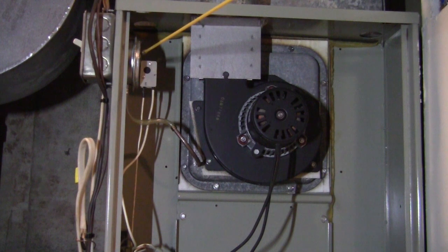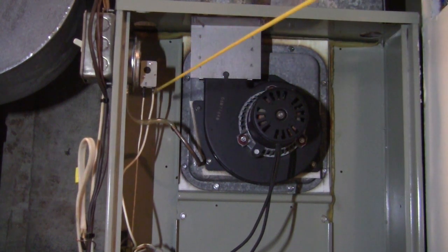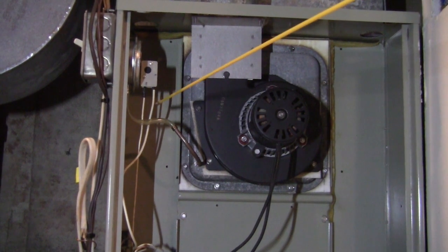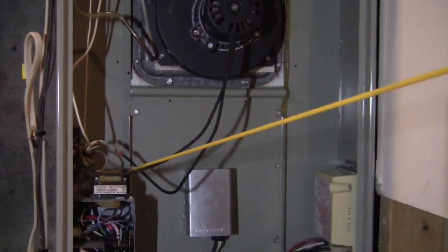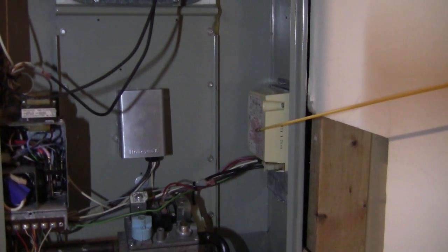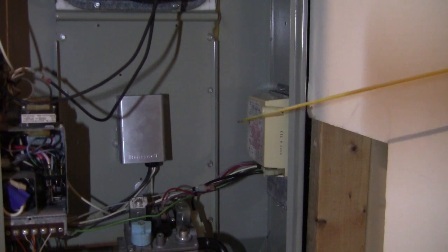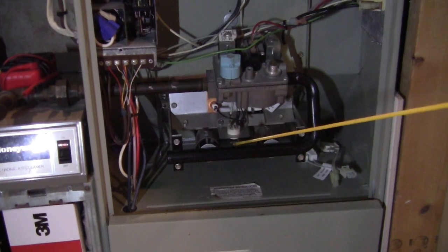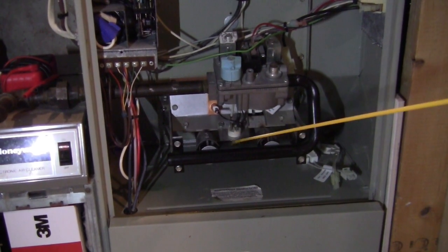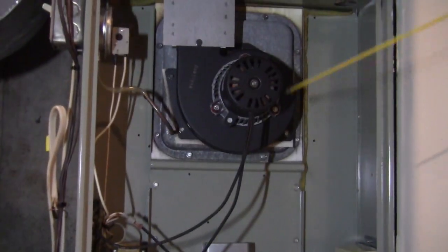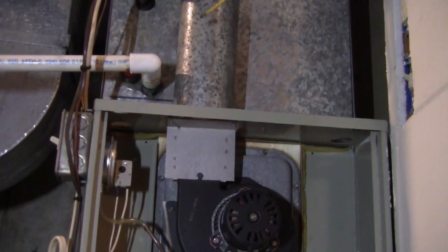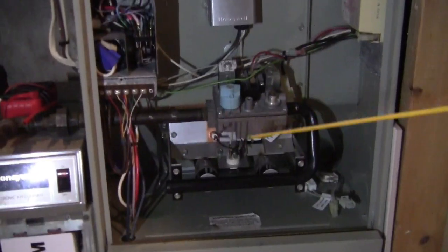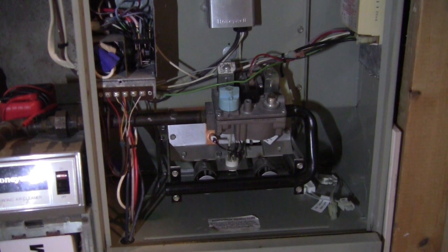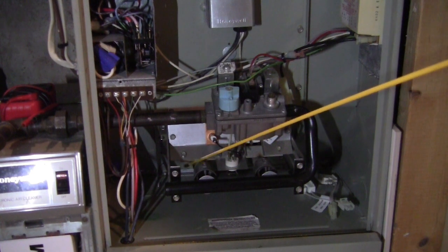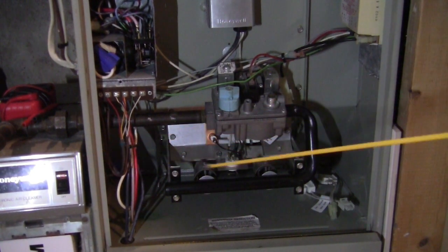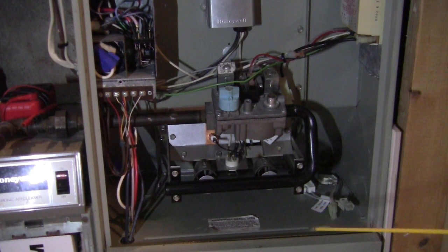So once you have vacuum from here, these two things will connect inside. This is called a pressure valve. Once the fan runs, you have vacuum through this, and these two things connect. Once they connect, it sends the signal from here to the controller, and the controller knows the vacuum exists. That means it's safe to give gas to the burner. If something happens in this section, the fan can suck it up to the outdoors, so it can be a little bit safe. And if this fan is not working and something leaks from here or from inside, and gets out to the living area, that can be a major danger for the family living in the home.